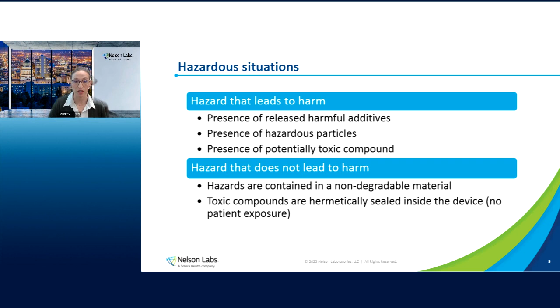Hazards that do not lead to harm. Hazards are contained in a non-degradable material. So maybe you have a colorant that has a carcinogen as part of the makeup, but it's in a matrix where it doesn't leach out, and you can prove that. Another one that doesn't lead to harm is that toxic compounds are hermetically sealed inside the device. So then there's no patient exposure. So I really think that those are important examples for us to consider when we go from hazard to harm to risk. Identifying if harm can occur is going to be critically important. And that's where we will apply a lot of our conversation today when we talk about some of the other changes in the document.